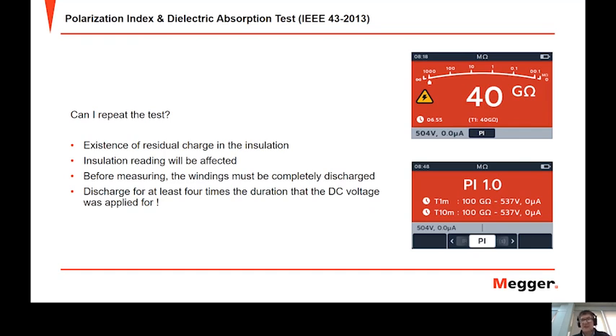So before retesting, you need to completely discharge the windings. And the standards say that you should discharge for at least 4 times the duration that you applied a DC voltage for previously. So if you've done 6 minutes on a PI test, you should discharge for at least 24 minutes before you rerun the test.